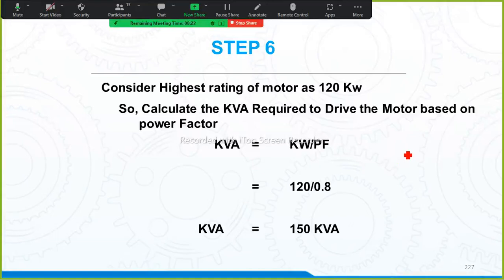Now calculate the kVA required to drive the motor. What is the exact kVA required to run the 120 kilowatt motor, that is your running kVA. Let us calculate. Calculate the kVA required to drive this motor based upon the power factor. kVA is equal to kW by power factor. So 120 divided by 0.8, we got 150 kVA. So this means I got the transformer size, 150 kVA.